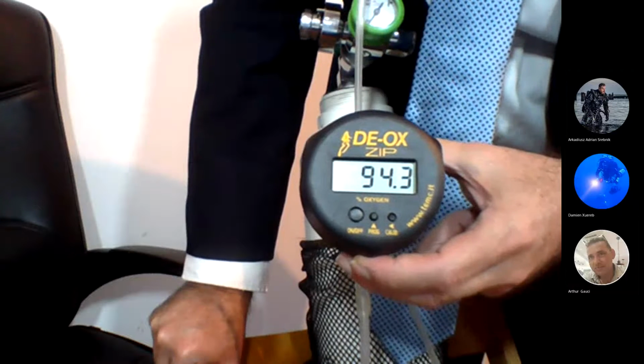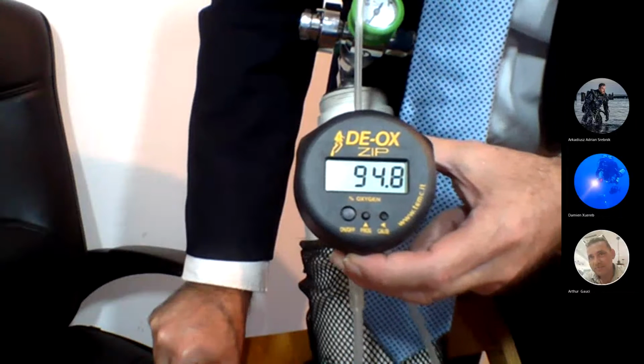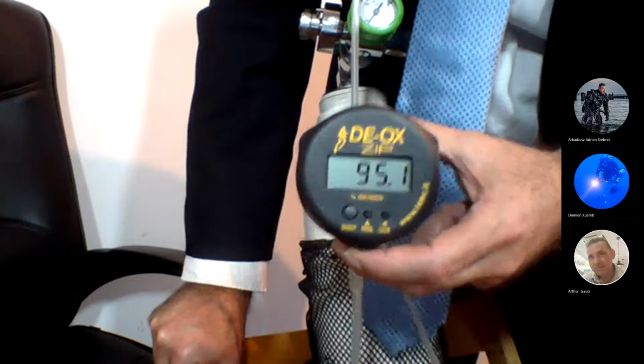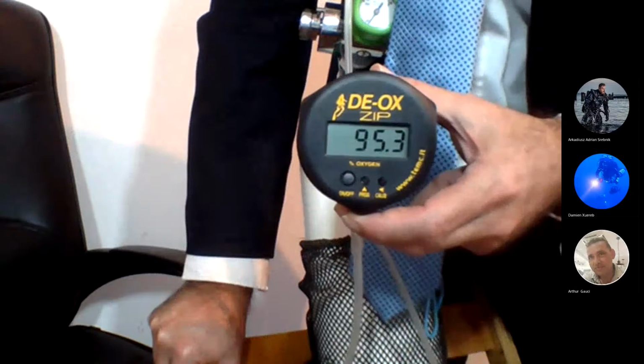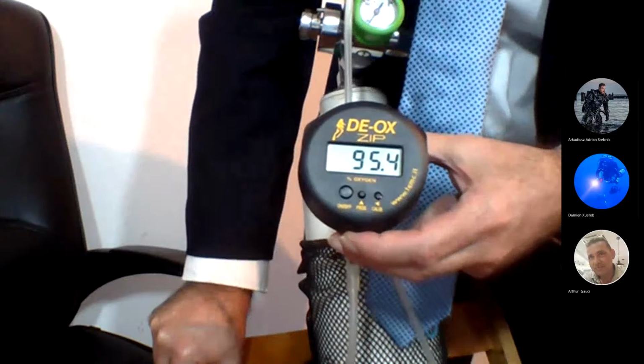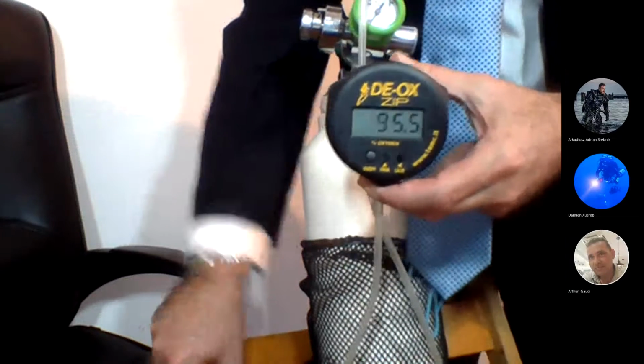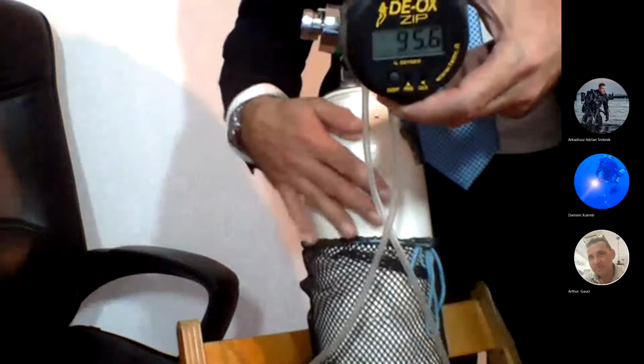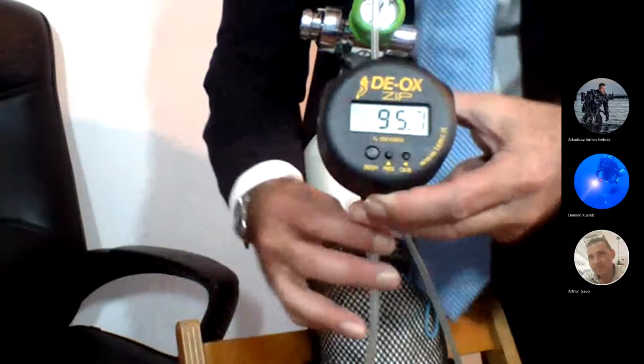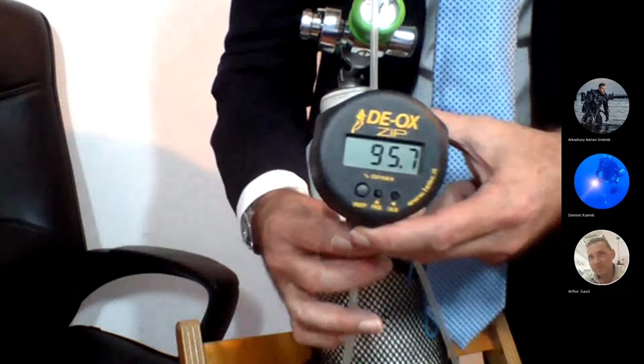It will give you an error, right? Yeah, of course, because it's more than 100. Correct. You see, it doesn't go to 100%. And this is not because the oxygen is not pure, but because we did the wrong calibration. You see? You can do it the other way as well, to make the percentage go low.